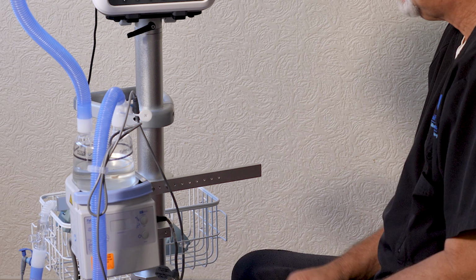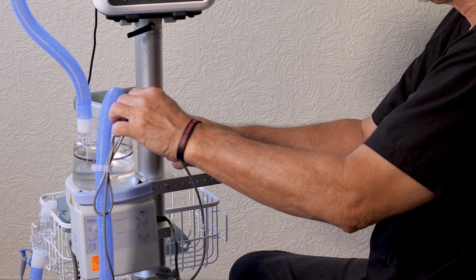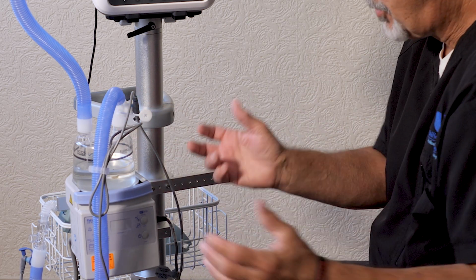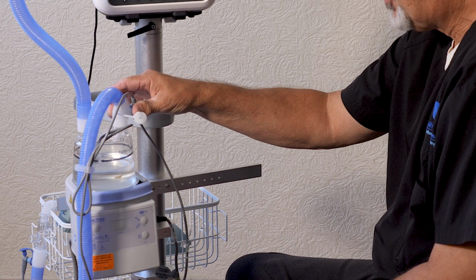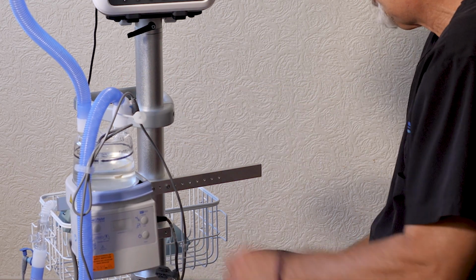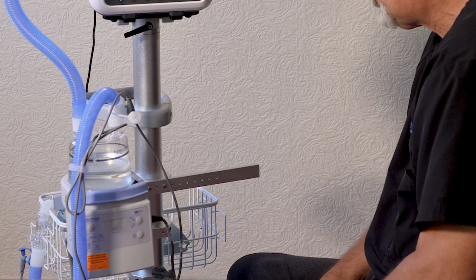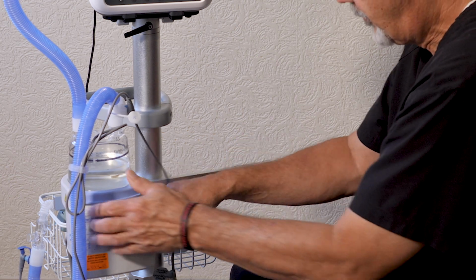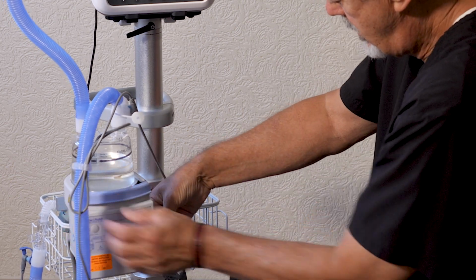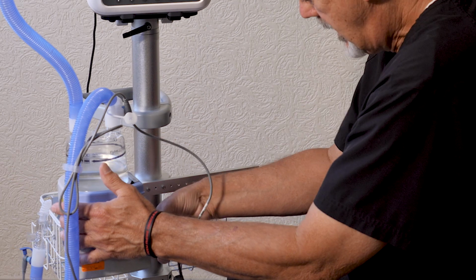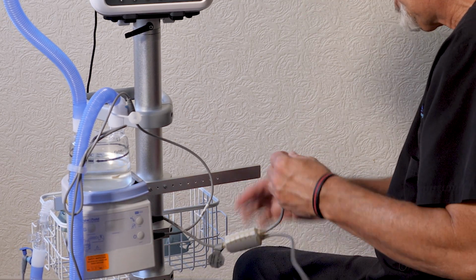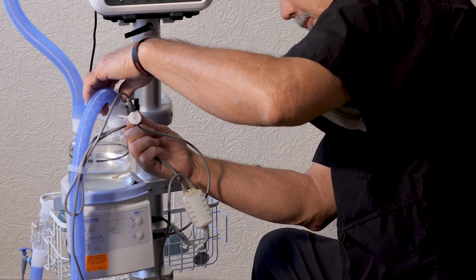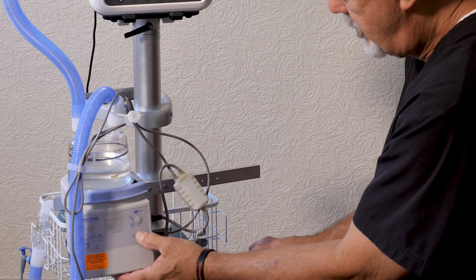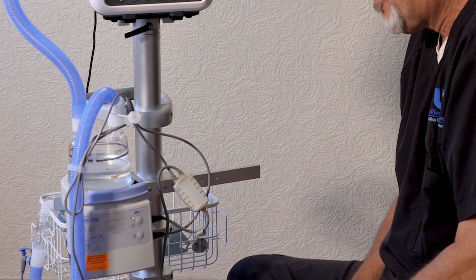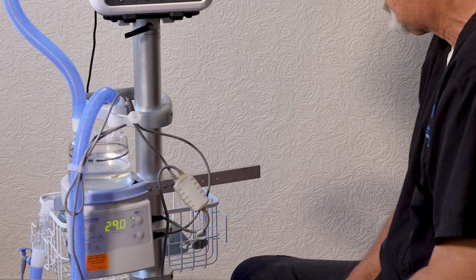Once you've done that, you're going to remove the temperature probe cable from the old circuit and reinsert it into the new circuit. And again, do not forget to wipe down the temperature probes with alcohol before you insert them back into the new circuit. And then you're going to reattach all the rest of your connections, just like this. Going to come over here, put that all the way in, and you're going to turn on the humidifier. Please don't forget to turn on the humidifier.